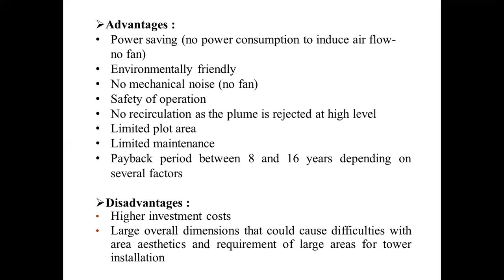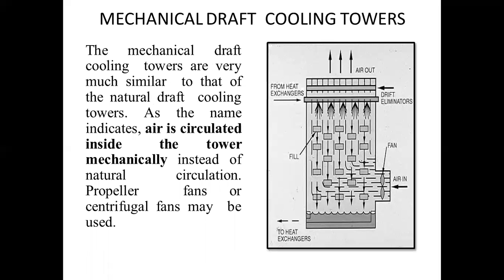The disadvantage is very high investment; the initial cost is very high. Large overall dimensions could cause difficulties with area aesthetics, and require large areas for tower installation, and the height is very large, which can sometimes be an obstruction for aeroplanes or helicopters or for defense purposes. That's why when there is a restriction, we go to mechanical draft cooling tower. In case of mechanical draft cooling tower, height is very less, but here we are using a fan.